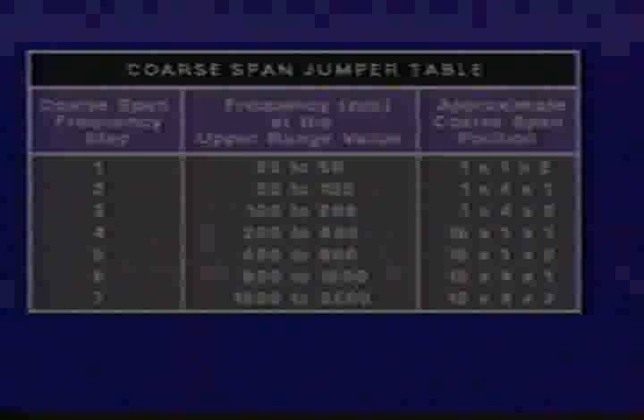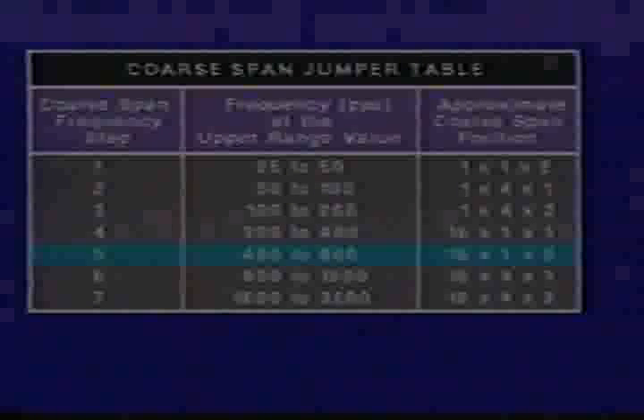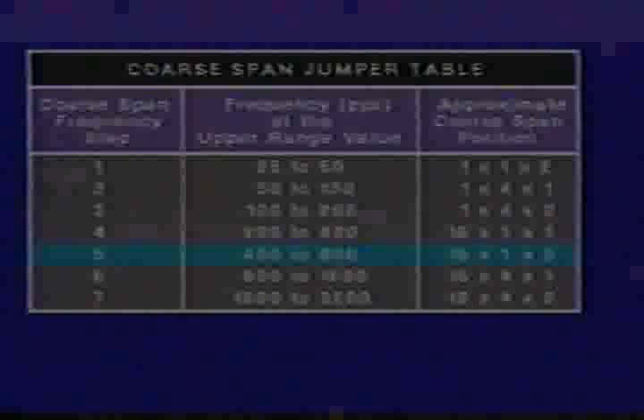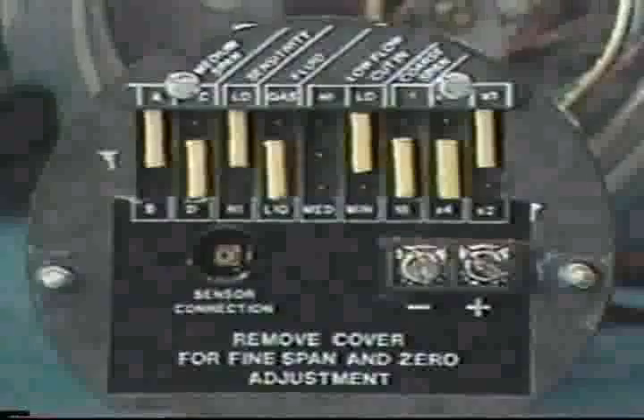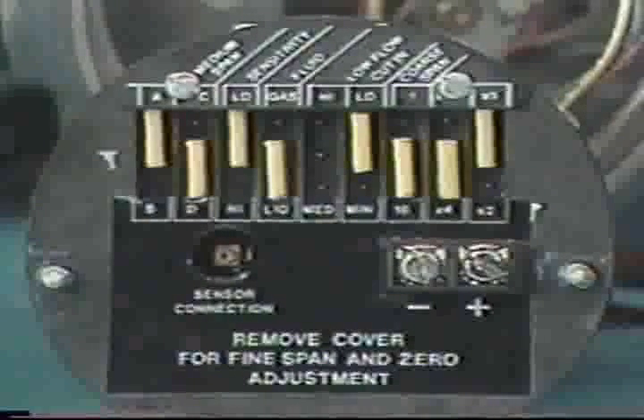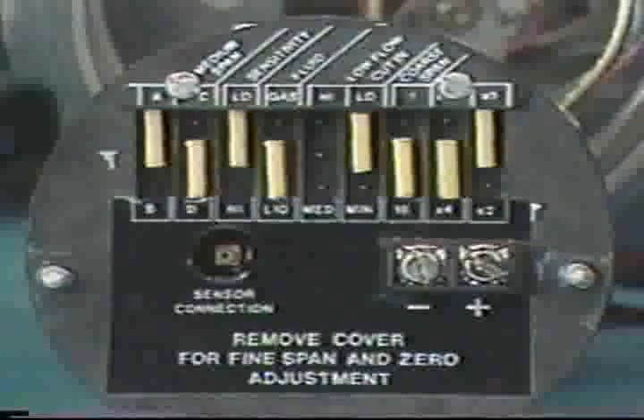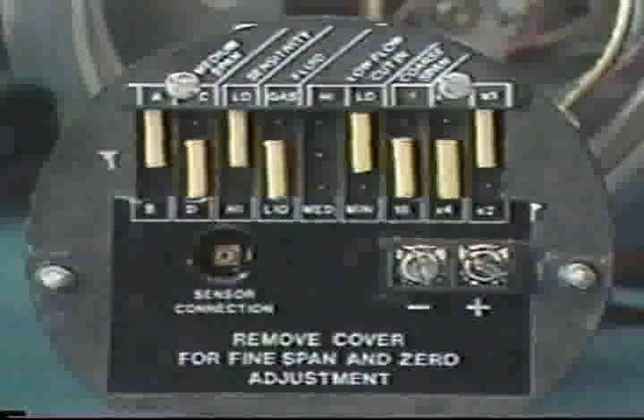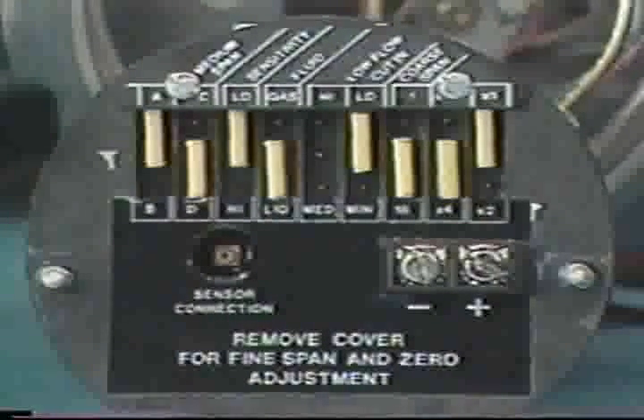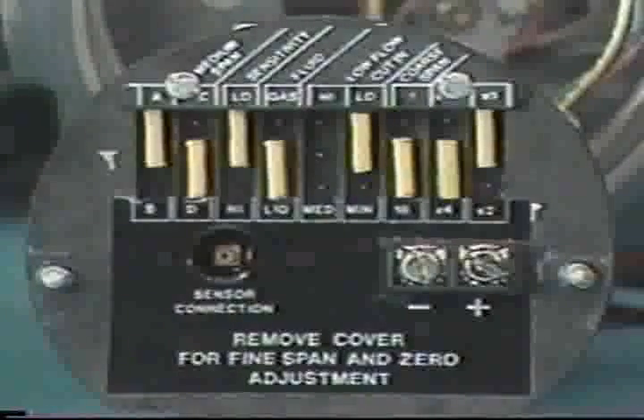The coarse span calibration prepares the instrument for the final fine calibration adjustment. The middle column of the coarse span jumper table lists the ranges of PPS frequencies at the upper range value. This line in the table indicates the setting for the coarse span jumpers at a vortex shedding frequency of 405 PPS. Here we can see the coarse span jumpers at the appropriate setting for 405 PPS. The medium span jumpers are set using another jumper table in the manufacturer's instructions.